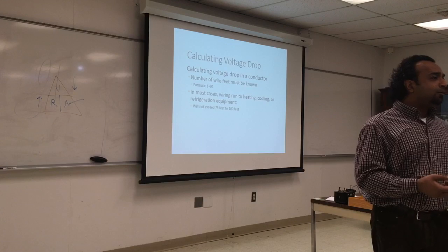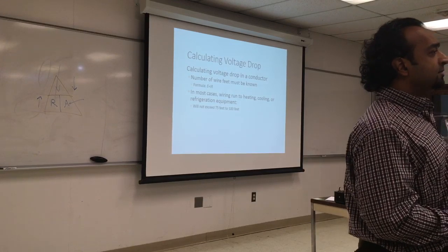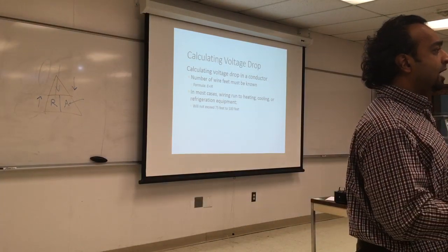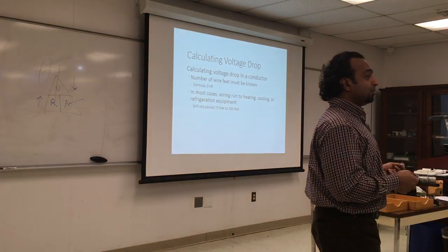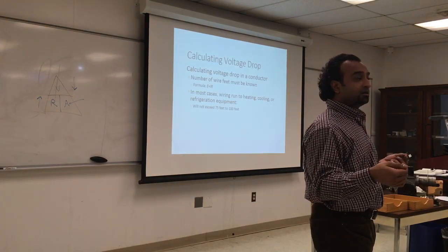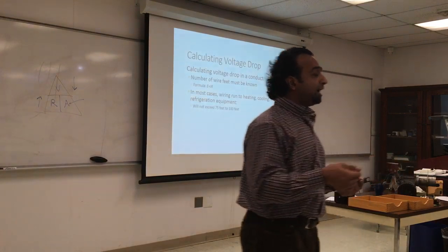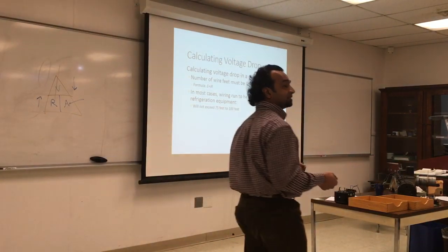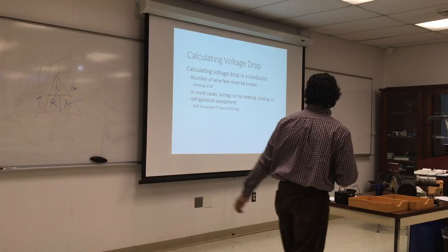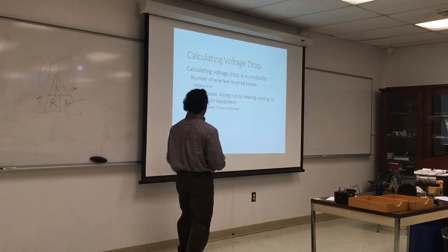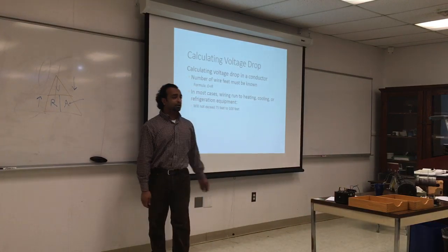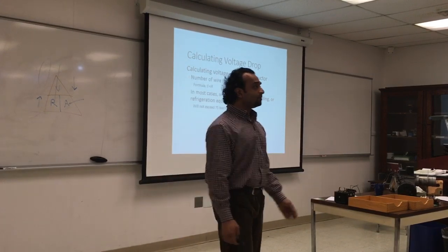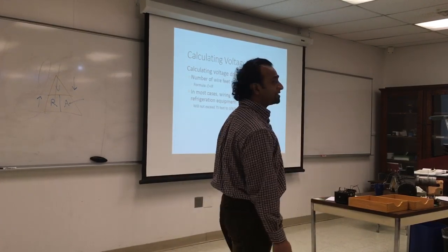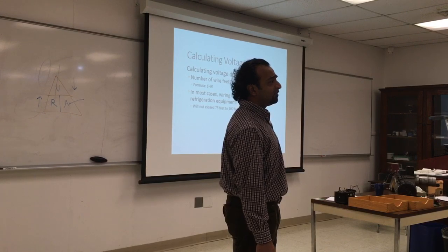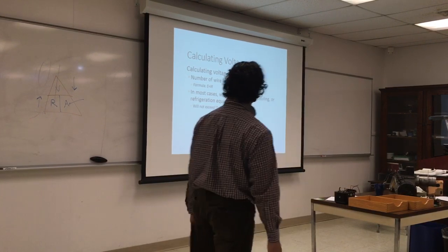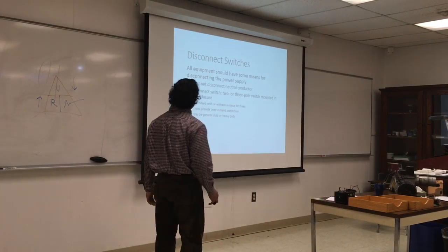And remember when we did the resistances in series, and after the first light bulb we saw some voltage drop, like 40 volts or so. So again, the wire is connected in series, so it will cause some voltage drop. So 75 to 100 feet, any more than that, then probably you will have to change the wiring. And the 100 feet is like 30 meters. That's far. That is pretty far. Disconnect switches.